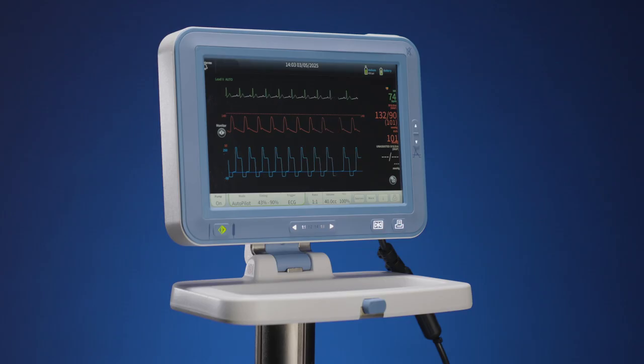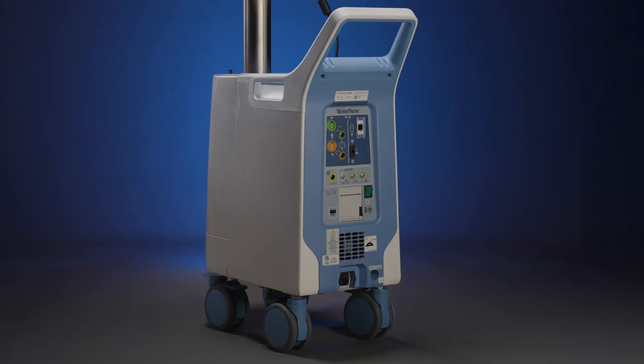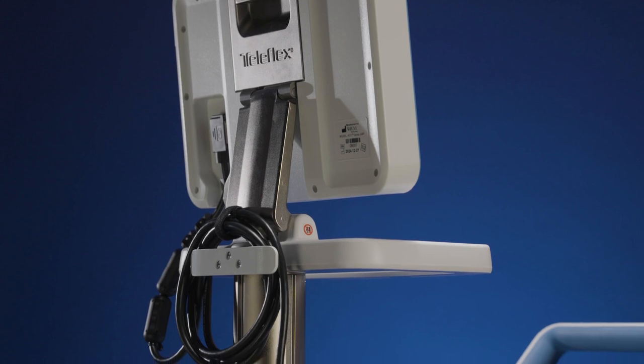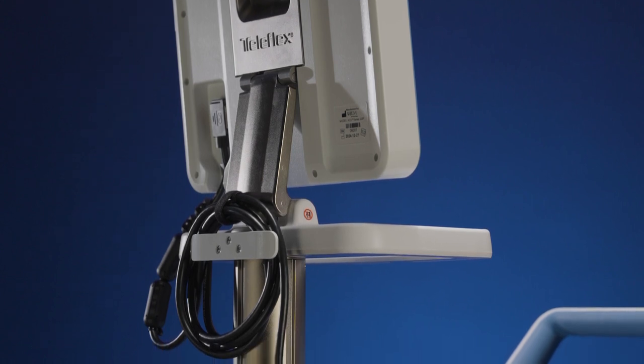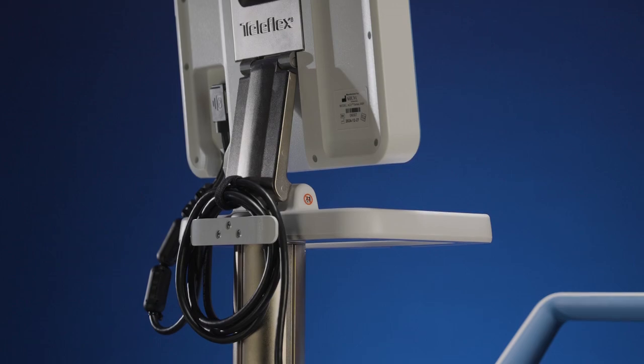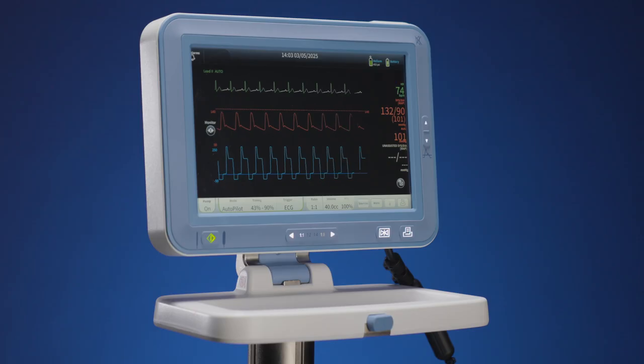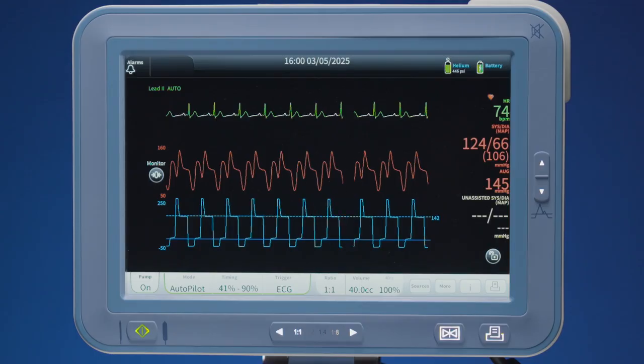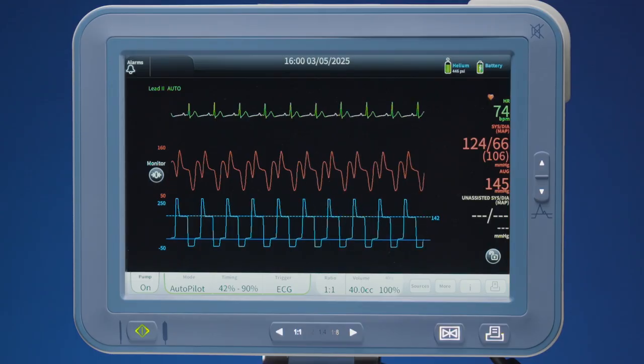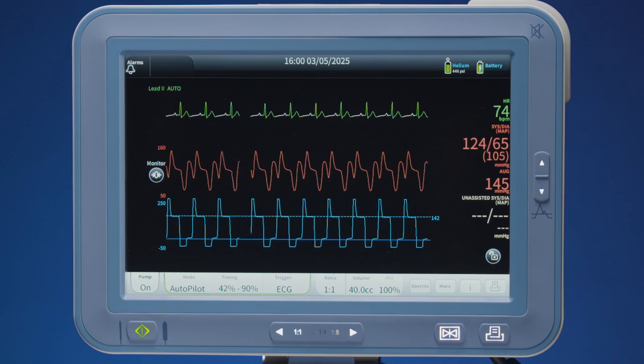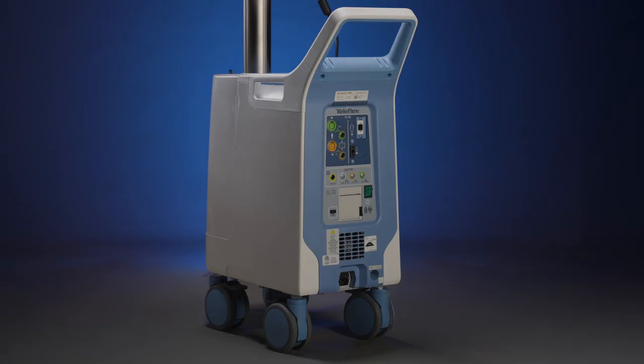The system consists of two components: the pump control display, which incorporates a touchscreen and keypad for system operation, and the pneumatic drive module with attached wheels. A 3.6-meter communication cable connects the pump control module to the pneumatic drive module. The detachable control display module houses the high-resolution LCD that shows the ECG, AP waveform, balloon pressure waveform, and hemodynamics. The pneumatic drive module contains the pumping system needed for IABP operation.